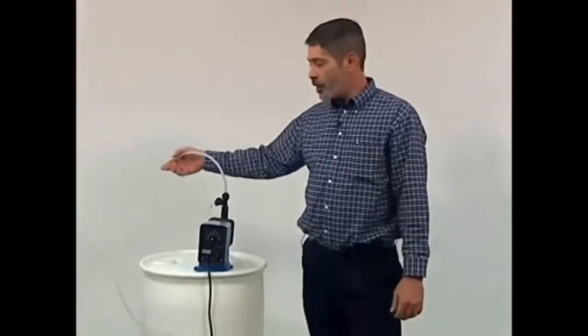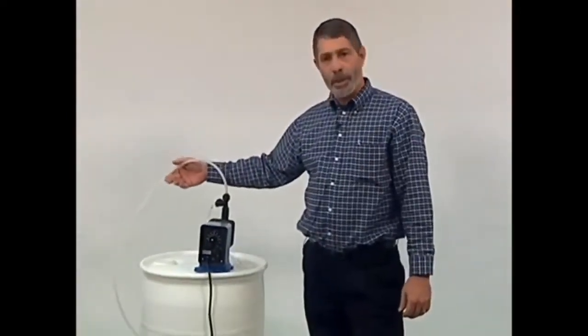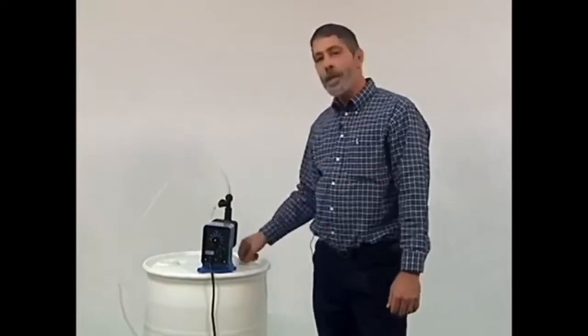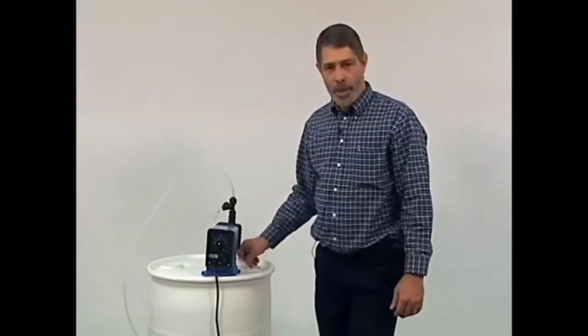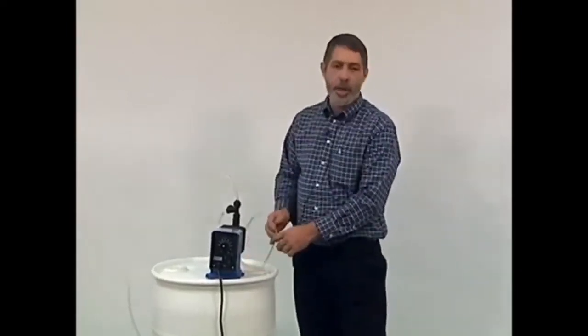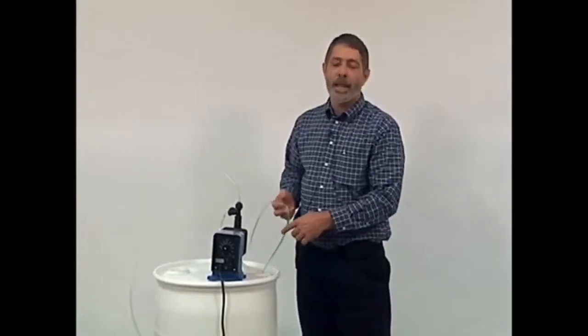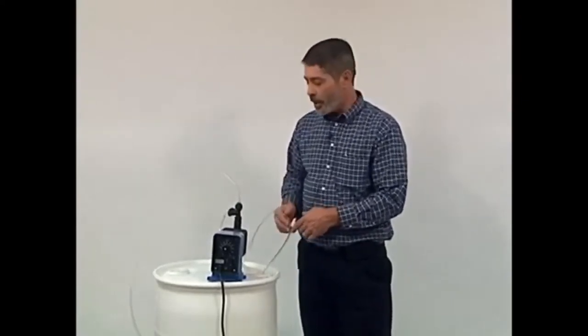Sometimes when we come into our customers' accounts, we find that our pump has lost prime. This could be age, wear, dirt, the customer changing the drum, but you need to be able to tell if your pump is primed fairly quickly. The first visual indicators are your tubing. Does your discharge tubing have chemical in it? If so, does your suction tubing have chemical in it? If there's no chemical in the suction line, then obviously we won't be moving any liquid.